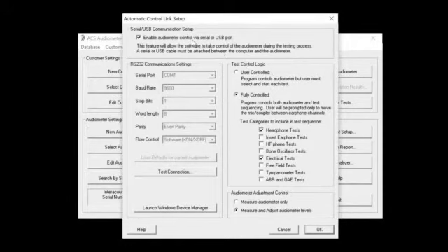We know that it's interfaced because that box is clicked and the program recognized that. Marks out these areas because it's interfaced and we have no control over that. No reason to retest the connection. We've done that already because we've transferred the serial number over. I can set this up and use user control, but again, you're taking over command. Get a little more sophisticated if you want to do that. Go ahead and do it. Leave it in fully controlled.